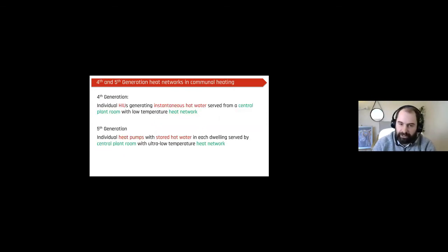So in summary, fourth and fifth generation heat networks in communal heating systems. Fourth generation are typically individual HIUs, heat interface units, in each dwelling, generating instantaneous hot water, served from a central plant room with a low temperature heat network. And fifth generation would be individual heat pumps in each dwelling with stored hot water in each dwelling, served by central plant with an ultra low temperature heat network. So both of these concepts have central plant rooms and they both have heat networks. The key difference is that in fourth generation you have an HIU generating instantaneous hot water, whereas in fifth generation you'll have a secondary heat pump, which will typically be storing water in a hot water cylinder within the dwelling.